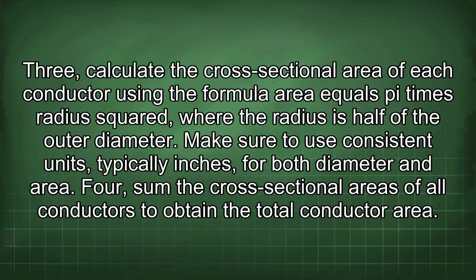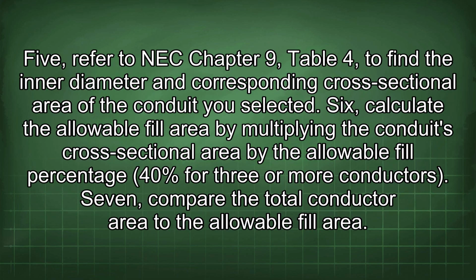3. Calculate the cross-sectional area of each conductor using the formula area equals pi times radius squared, where the radius is half of the outer diameter. Make sure to use consistent units, typically inches, for both diameter and area. 4. Sum the cross-sectional areas of all conductors to obtain the total conductor area. 5. Refer to NEC Chapter 9, Table 4, to find the inner diameter and corresponding cross-sectional area of the conduit you selected. 6. Calculate the allowable fill area by multiplying the conduit's cross-sectional area by the allowable fill percentage, 40% for 3 or more conductors.